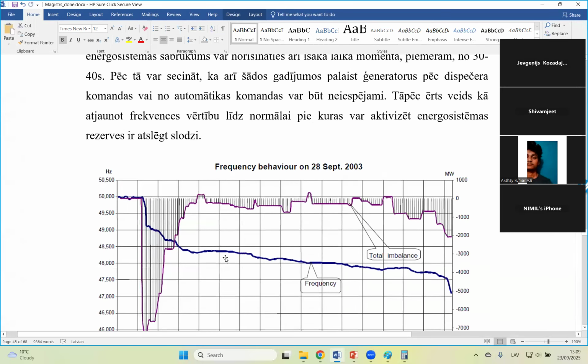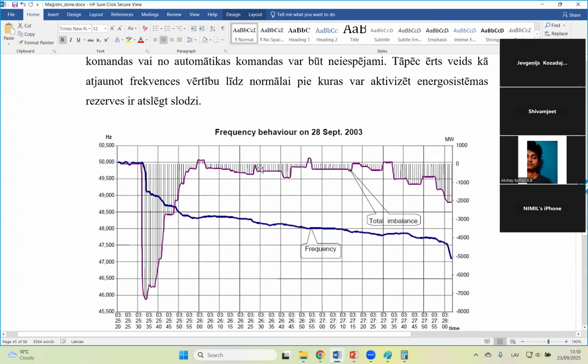Okay, what to do? We lose generation power. That's why we need to disconnect more load to restore this balance as well. And here we can see we start to lose generators, power losses. Here you see these surges of imbalance. Okay, imbalance, come back, disconnect load, come back, disconnect load, and so on, until we disconnect all possible load connected to this automation. And as a result, the frequency is lower, more generators are lost, and as a result here you see the frequency drops to 47 hertz and total blackout. We lose everything.